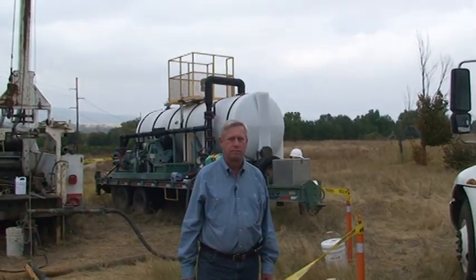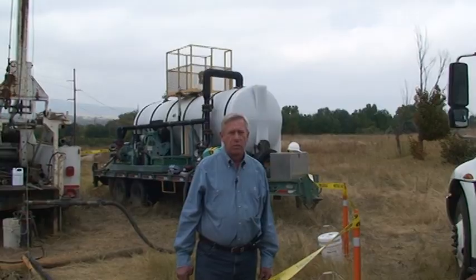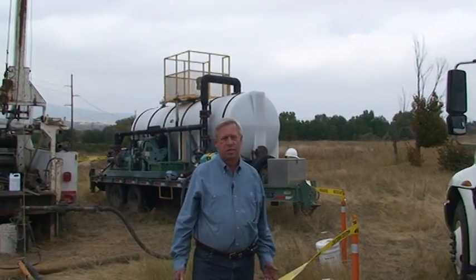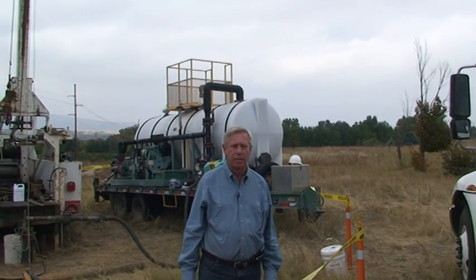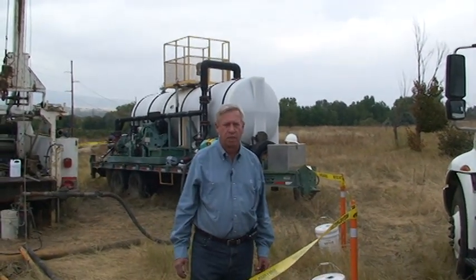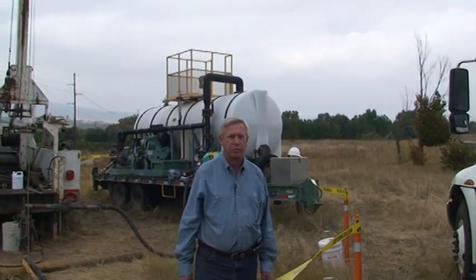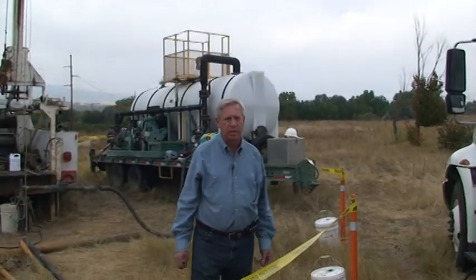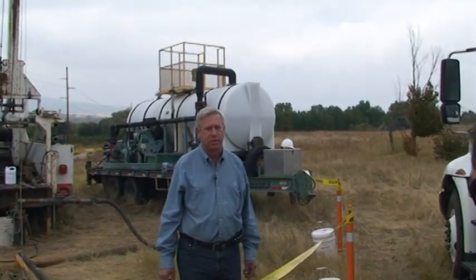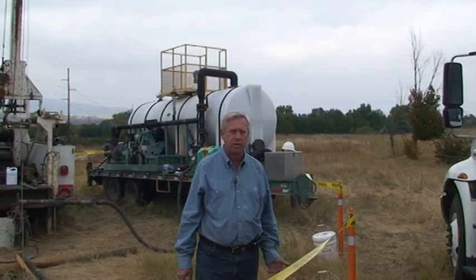So you guys have determined it has failed. What are the steps to make it not fail? In a sense, failure means it's lost production from the permitted and decreed production level of 125 gallons a minute. The latest test on it had it down to 18 gallons per minute. So that means failure, in the sense that it's not really a producing well that's particularly good for the city to use.